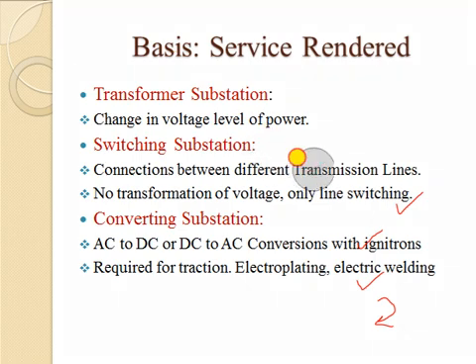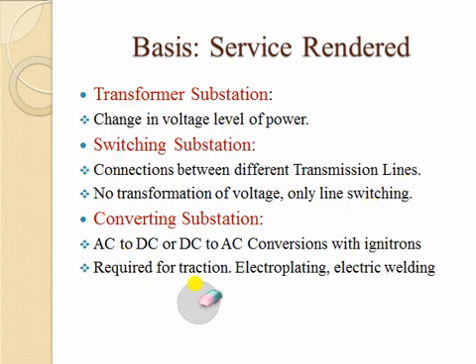Depending upon what type of service is being rendered, substations are classified as transformer substations — the routine concept of changing the voltage level of power. But there are some substations that may not have a transformer at all. They simply play the role of switching transmission lines, playing a very important role in protection systems, system isolation, and operating as junction points in the transmission system. These are called switching substations — no voltage transformation, only line switching.